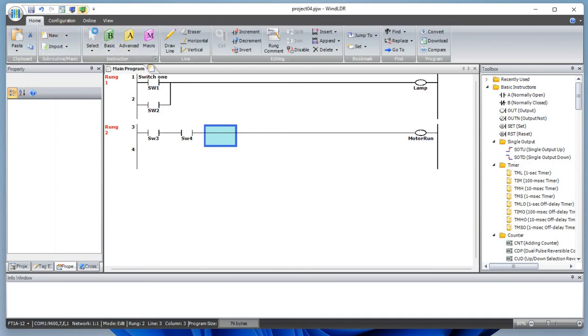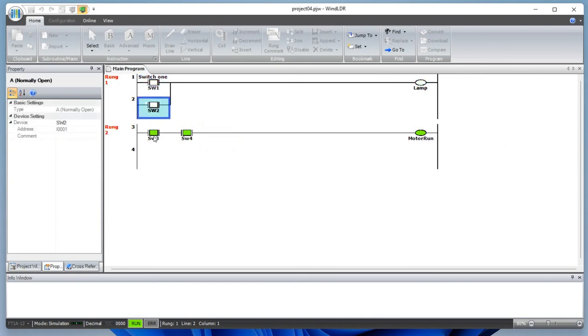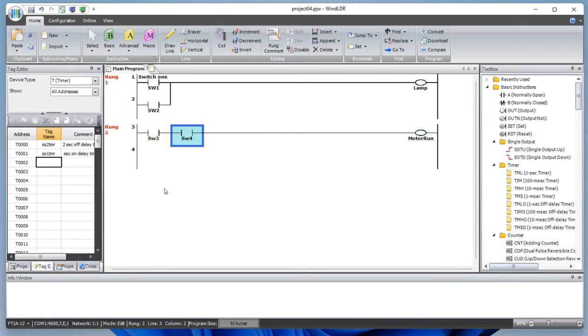In order to turn on the motor, either switch alone will not work — both switches must be turned on. Let's simulate: only when switch three and switch four are both on does the motor run. If switch three is off, the motor won't turn on. If both are off, the motor won't run. This is AND logic. You can also use a normally closed contact here — for example, in an E-stop circuit to stop the motor during an emergency.